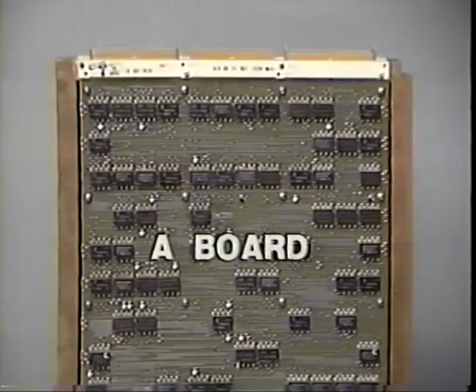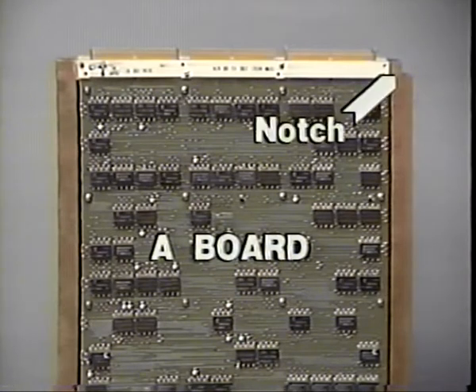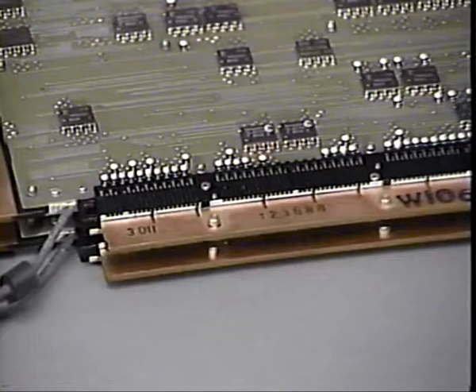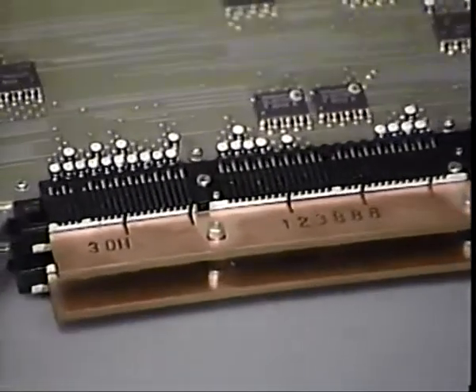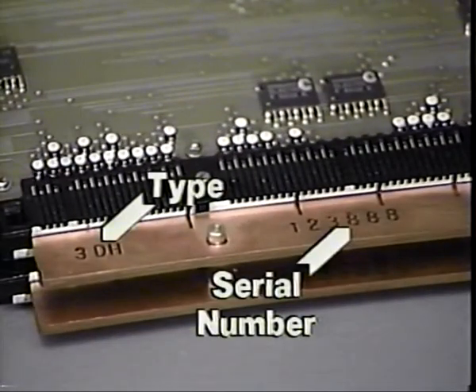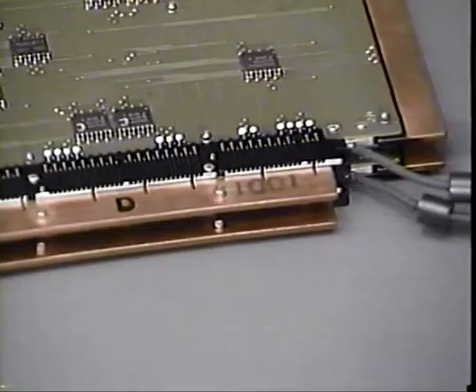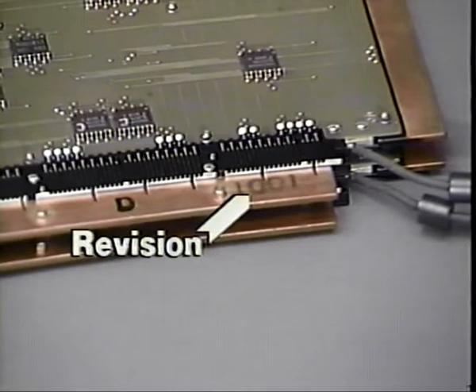Looking at the top of the module, the A board, you'll notice that the module cold plates have a notch in the upper right-hand corner. This notch prevents improper installation in the mainframe. The module can only be installed with the A board on top. The module type and serial number are also located on the A board. The module revision is found on the D board.